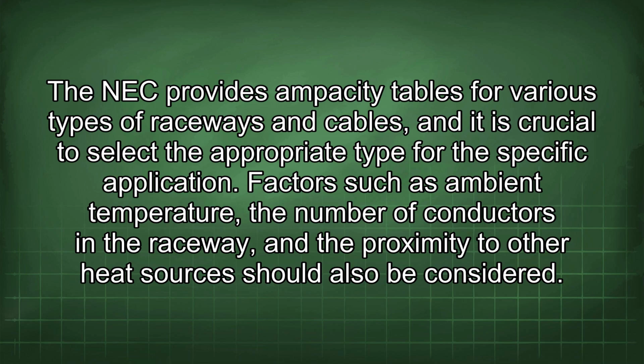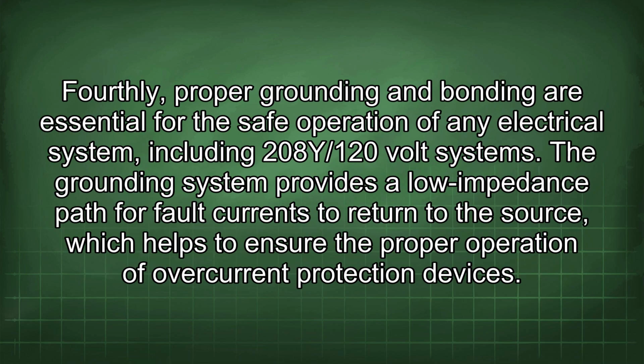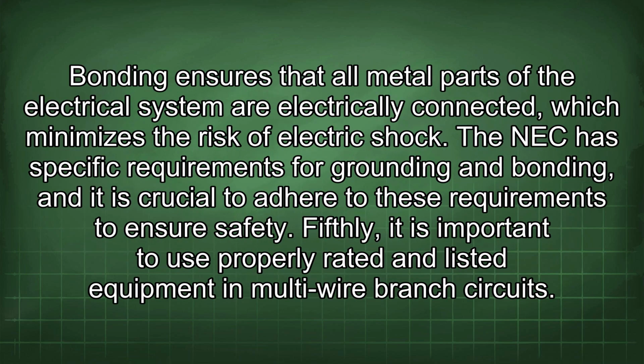Factors such as ambient temperature, the number of conductors in the raceway, and the proximity to other heat sources should also be considered. Fourthly, proper grounding and bonding are essential for the safe operation of any electrical system, including 208Y/120 volt systems. The grounding system provides a low impedance path for fault currents to return to the source, which helps to ensure the proper operation of overcurrent protection devices. Bonding ensures that all metal parts of the electrical system are electrically connected, which minimizes the risk of electric shock. The NEC has specific requirements for grounding and bonding, and it is crucial to adhere to these requirements to ensure safety.